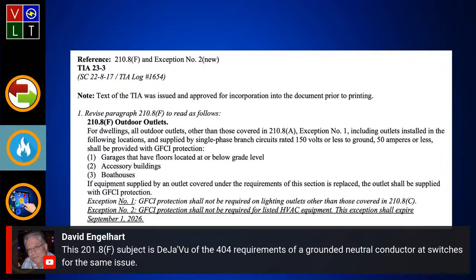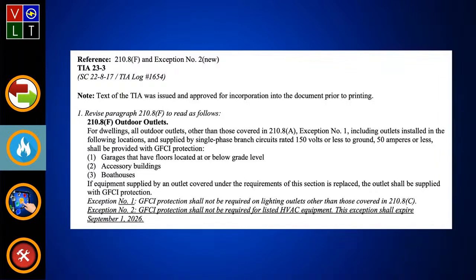Yeah, and I do agree with that, David. David says that the 210.8F argument kind of stems from some arguments we had with 404, where they had some switch devices that had leakage current. They actually were using the equipment ground as a neutral if you didn't have a neutral at that switch location. And that was kind of a problematic thing. And I think those switches have actually been outlawed, but because they do have that leakage current. Leakage current's a bad thing.